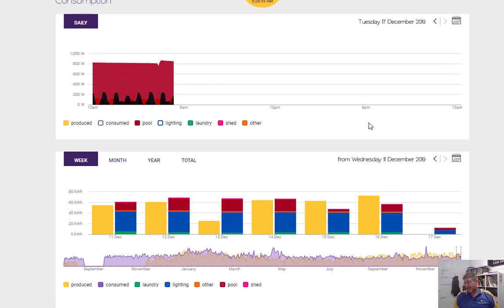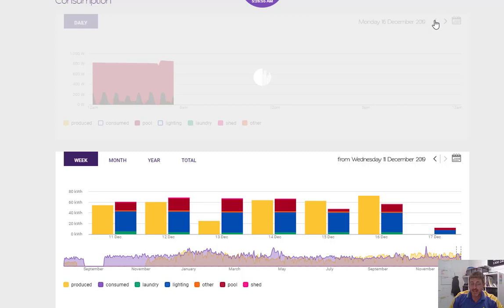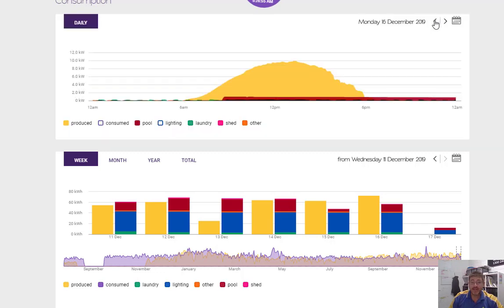What would happen is the customer would get a bill 3 months later and say, hey, my energy usage has gone up, I haven't saved as much, but you've already spent that money. There's nothing you can do about it. So this is a great example. I'll be able to get onto them today and give them a call and say, hey, it looks like the pool pump has actually gone back to being manual, which does happen. It's just staff dealing with staff. They turn the timer off, it's gone back to manual, and therefore this is going to use energy all night.